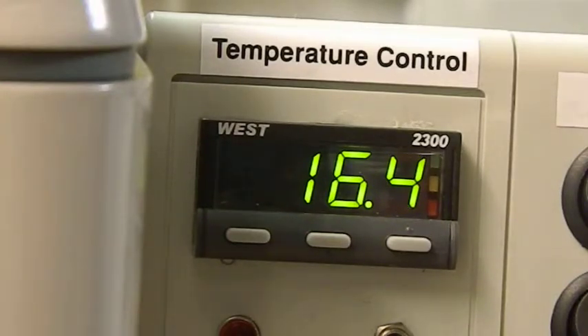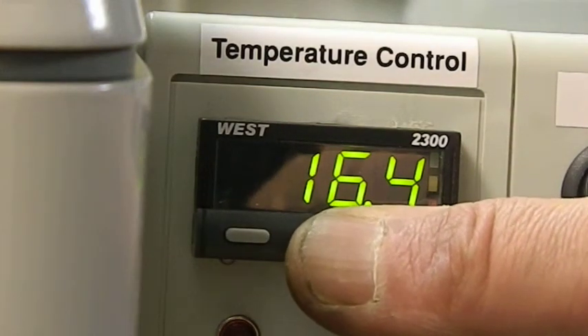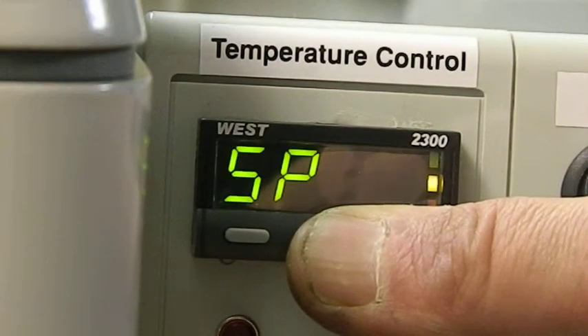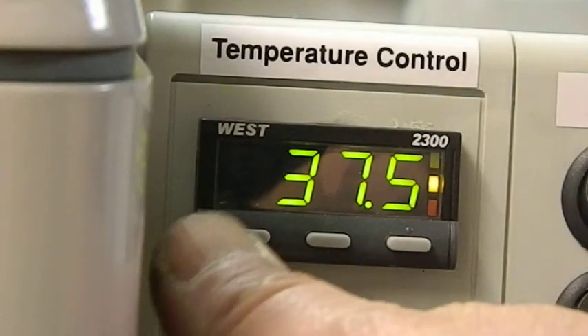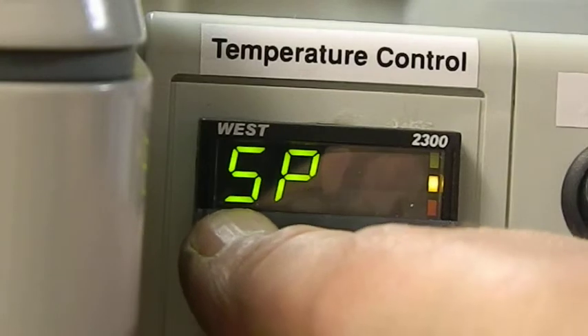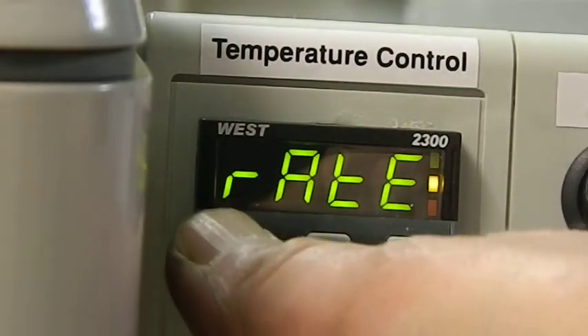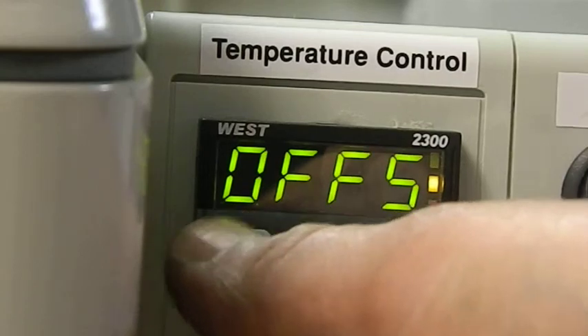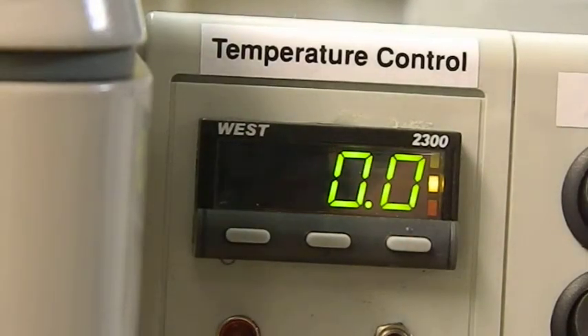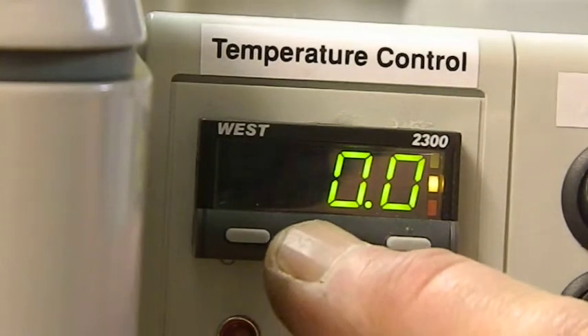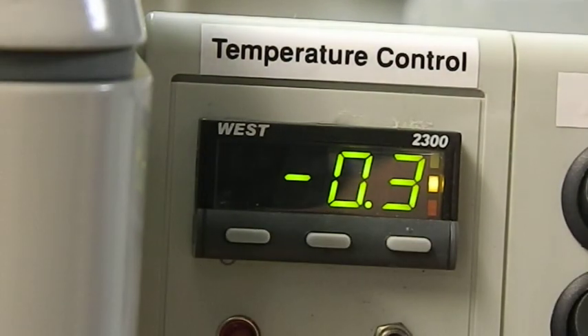Okay, to get to the parameter to calibrate, you press the right and centre buttons together and hold them until SP comes up. Okay, you now have to flick through the parameters, so you keep pressing and releasing the left hand button until you get to OFFS. This is offset. The standard setting on this is 0, and that means that there is no differential between the sensor reading and the actual temperature in the machine, but we know that the controller is 0.3 high, so we need to put in a value of minus 0.3.